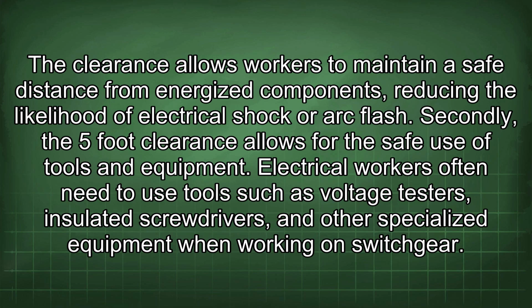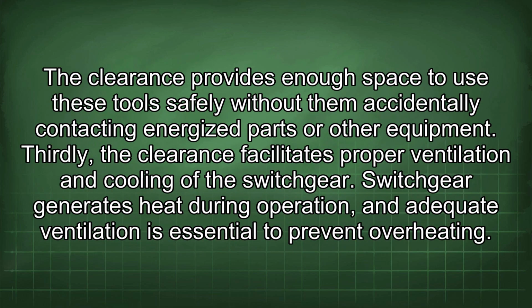Secondly, the 5-foot clearance allows for the safe use of tools and equipment. Electrical workers often need to use tools such as voltage testers, insulated screwdrivers, and other specialized equipment when working on switchgear. The clearance provides enough space to use these tools safely without them accidentally contacting energized parts or other equipment. Thirdly, the clearance facilitates proper ventilation and cooling of the switchgear. Switchgear generates heat during operation, and adequate ventilation is essential to prevent overheating.